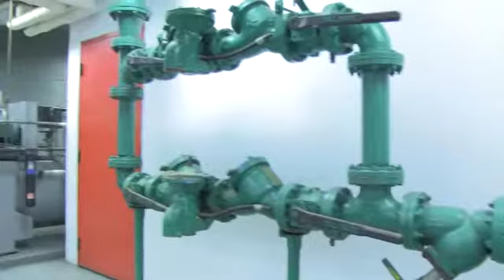Just to the left, there's an air compressor, which you can hear running right now. Air compressors are used to pump pneumatic air throughout the building for the purposes of controls, turning thermostats up and down, moving dampers and things like that. It's all done by pneumatic air pressure, so that air compressor is part of that. That's kind of old technology by today's standards.